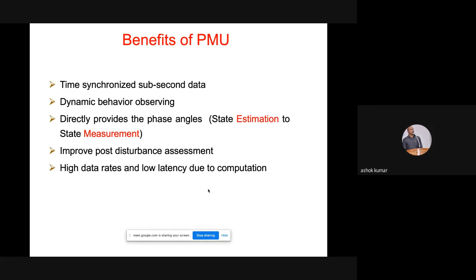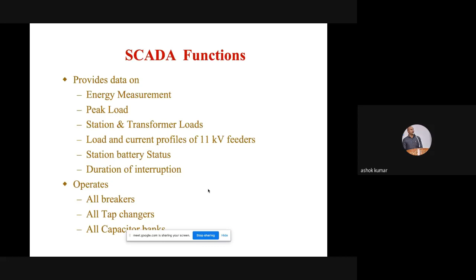Presently, SCADA functions are being used everywhere. SCADA provides energy management - it tells you the peak load, the status of the transformer load it operates, the status of the breaker, the tap changer, OLTC (on-load tap changer), and APFC, automatic power factor controller, with the help of capacitor banks. All these things can be controlled with SCADA functions. You might have seen this in RLDC, regional load dispatch center, in your area.